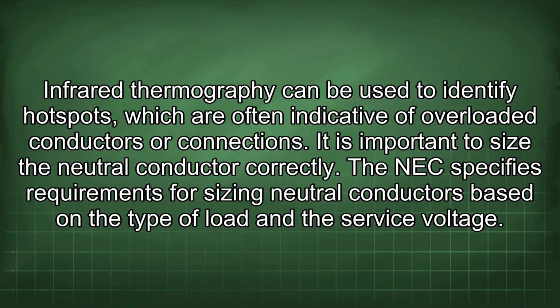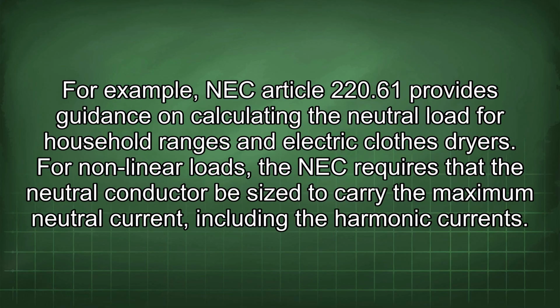It is important to size the neutral conductor correctly. The NEC specifies requirements for sizing neutral conductors based on the type of load and the service voltage. For example, NEC Article 220.61 provides guidance on calculating the neutral load for household ranges and electric clothes dryers.